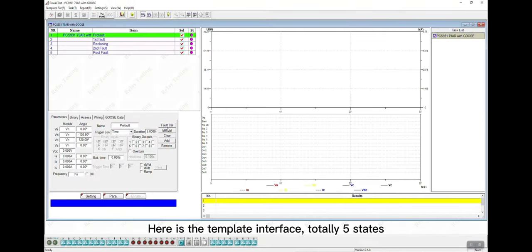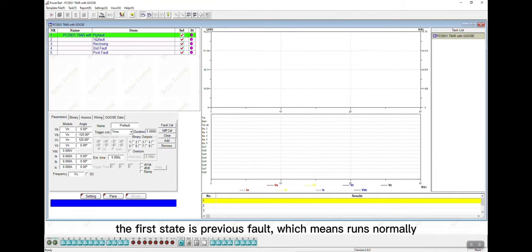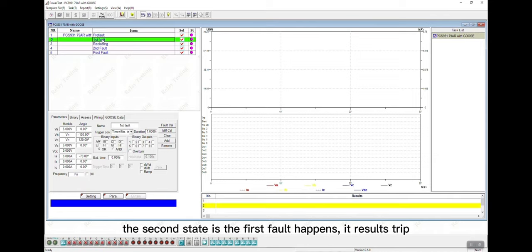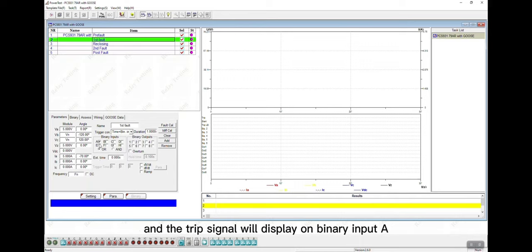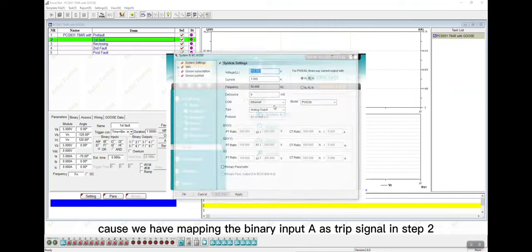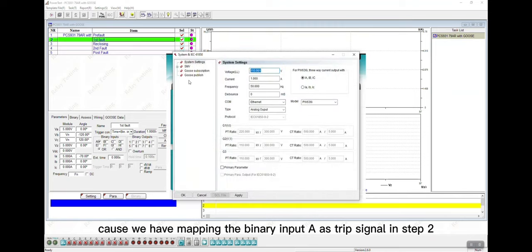Here is the template interface, totally 5 states. The first state is Prefault, which means runs normally. The second state is the first fault happens, it results trip. And the trip signal will display on binary input A, because we have mapped the binary input A as trip signal in step 2.